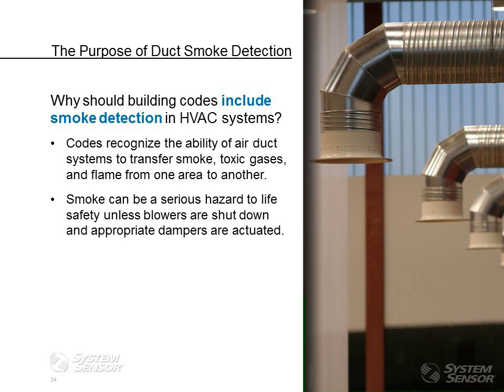So, what is the purpose of duct smoke detection? Why should building codes include smoke detection in the HVAC systems? The reason we do is that the codes, both the International Mechanical Code and NFPA, recognize the ability of air duct systems to transfer smoke, toxic gases, and flames from one area to another. Smoke can be a serious hazard to life safety unless blowers are shut down and appropriate dampers are actuated.